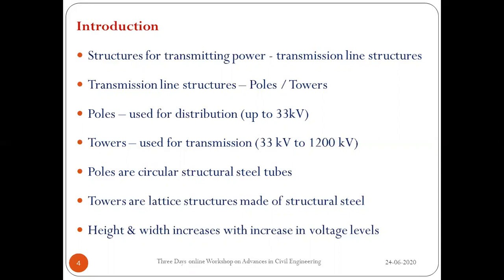Poles are normally used up to 33 kV. Poles are made up of circular cross-sections, either built-up or ready-made sections for smaller kV levels. They can be a single pole, monopole, or bipole. For higher voltage levels, we use lattice-type structures called towers, adopted from 33 kV to 1200 kV. Towers are normally truncated square pyramid shapes with cross arms to hold the conductors and earth wire. The height and width of the tower increases with the increase in voltage levels.